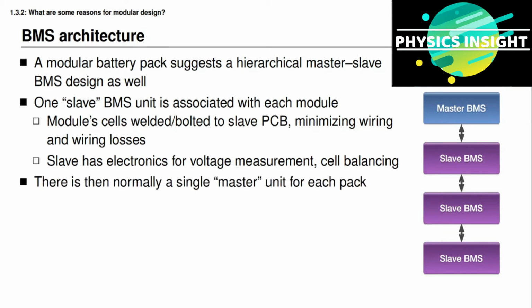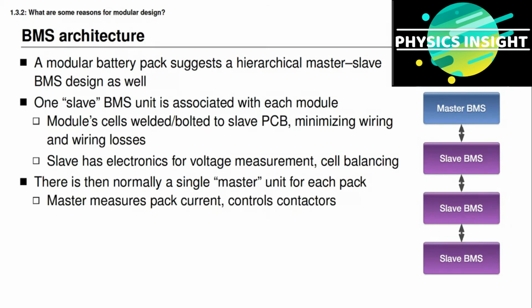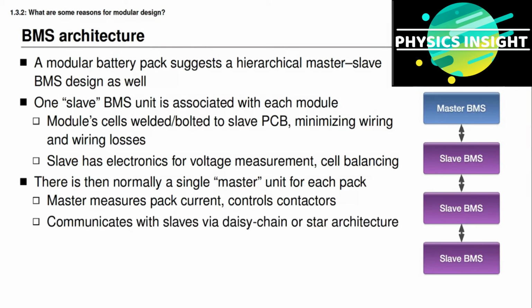There's commonly a single master unit for every battery pack, and the master unit does the supervisory control of everything overall. It's directly connected to the circuitry that manages and measures the overall battery pack current and opens and closes the contactors. The master unit communicates with all of the slaves, and it can do this using a daisy chain architecture like the one drawn in the illustration on this slide.